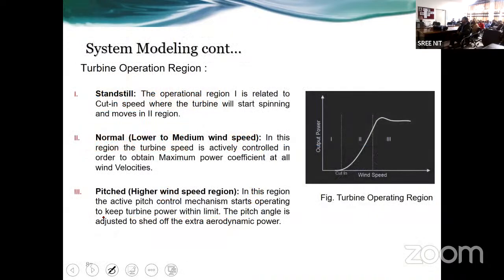There are different modes. Standstill operation may be there where no power is generated, the first region. The second is the normal region, from lower to maximum wind power. This is the second region where you have to perform MPPT. Here the power is a cubic function of the wind speed; you can see the output power varying with the wind speed. But above rated or higher speed, you have to maintain it within the limit. So the higher the speed, the more you keep on pitching. That is known as pitch operation at higher speed.